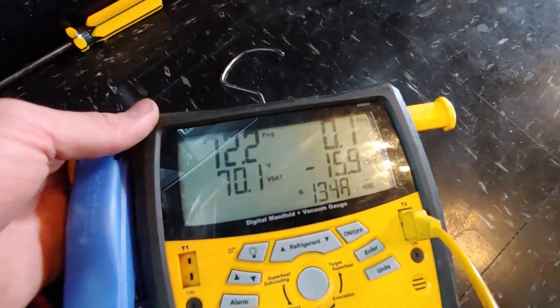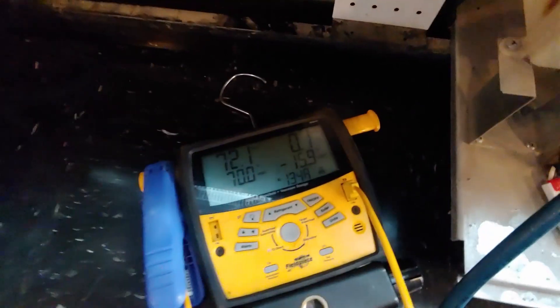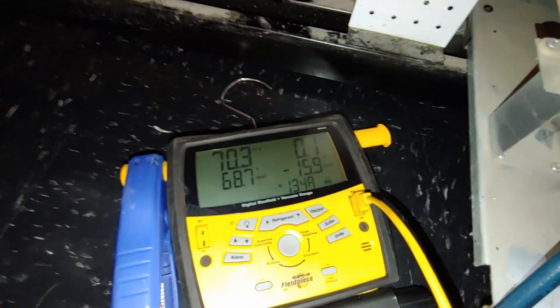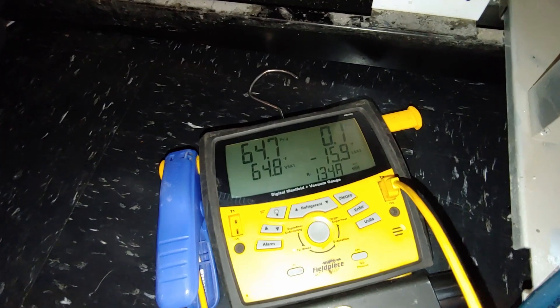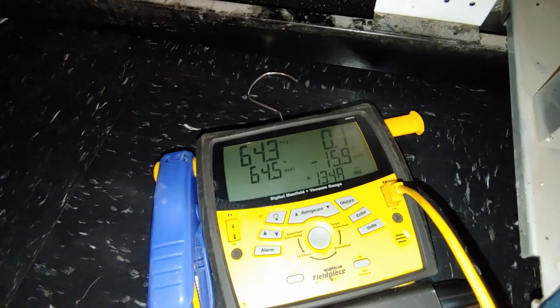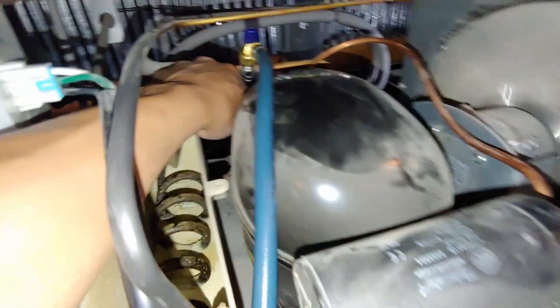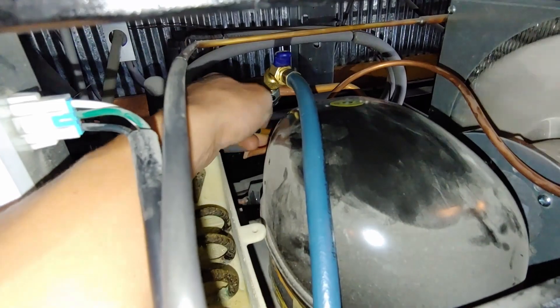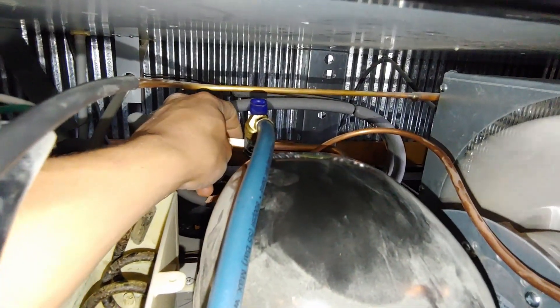Here we have an example of a failed compressor that is no longer pumping. We're going to plug the compressor back in — watch the amp draw. Bummer, compressor is bad. The outlet line right here is not getting even warm, slightly warm toward the compressor. This line is ever so slightly cold.